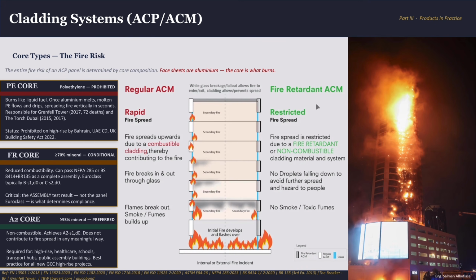Here we have another example, the fire retardant ACM and the regular ACM, the aluminum composite material. Remember, the face sheets are aluminum both ways. The core is what burns. PE core, FR core, A2 core. So the one on the right is restricted, no spread, because the material is fire retardant and non-combustible, and there are no droplets falling down to avoid further spread and hazard to people. No smoke, no toxic fumes. Just like this, the droplets keep falling down. While the one on the left, let's say the PE core, the fire will keep increasing floor by floor.